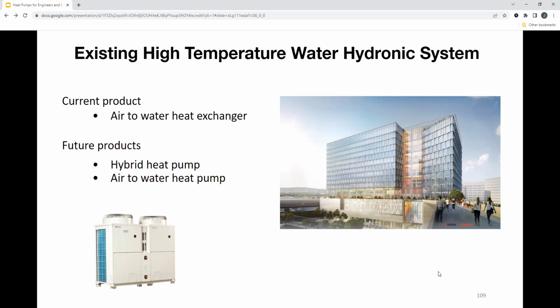And also there's another product. It's not really for retrofitting, but it is a hybrid heat pump system. And what I mean by that is you actually use the same air source condensers you'd see outside for a traditional heat pump system. However, that refrigerant line is going into the building and connecting to this hybrid controller. And what that's doing is actually having a heat exchange between refrigerant and water. And then you have 2 pipes of water going out to each individual fan coil unit. So that's manufacturer specific. You cannot add different types of water fan coil units. So we are manufacturing it.